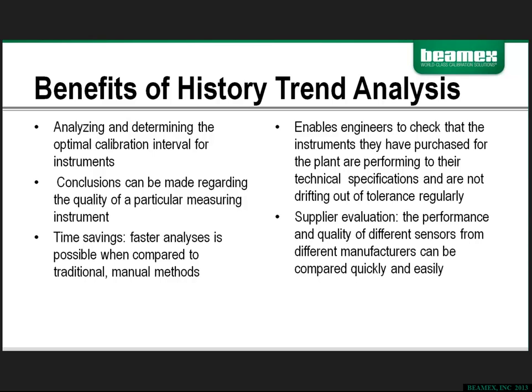A significant out of tolerance condition typically is a red flag to an operator or an end user that this instrument has drifted much more than was anticipated during that particular calibration cycle. And typically a review would need to be performed at that point to determine what calibration cycle would need to be put in place in order to keep that instrument in tolerance. A significant event when it comes to calibration has the ability to not only impact production, but it can seriously affect the end product, because the instrument itself was so far out of specifications that the results gained through the process may have been well outside the specs that were intended through the engineering process.